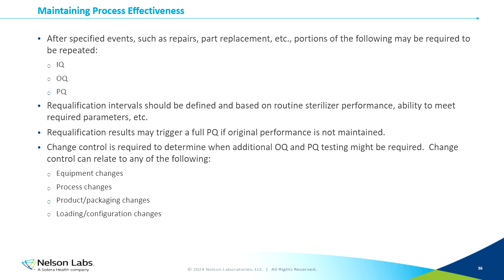any changes that occur. We also need to make sure that we define our requalification intervals and that we look at routine cycle, routine sterilizer performance, the ability to meet the required parameters, et cetera, when we determine that requalification interval. And requalification results could trigger a full PQ if original performance is not maintained. If we see a situation where we are not maintaining the performance that was established during the validation, we may need to requalify the entire process.